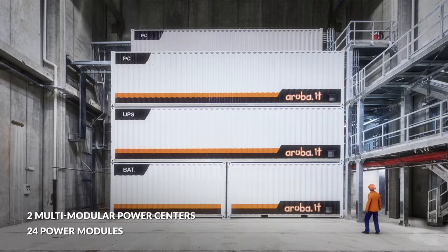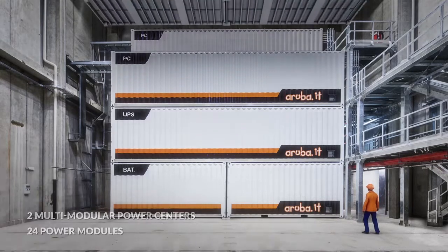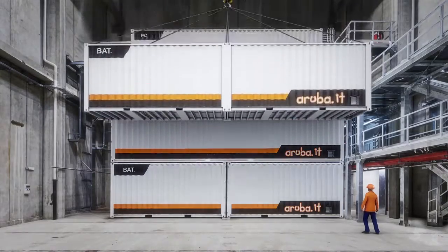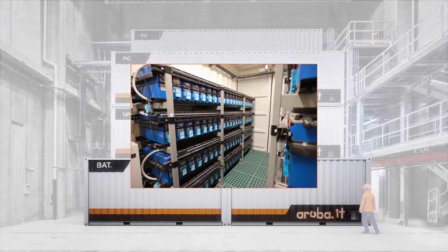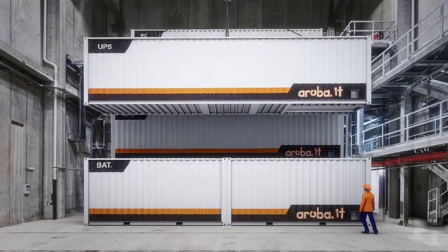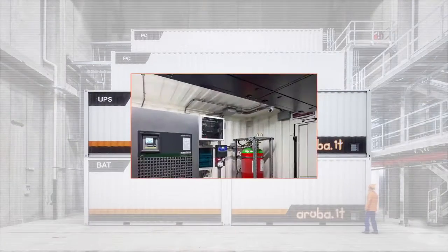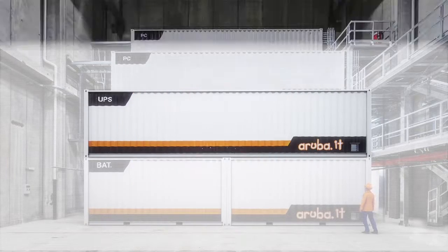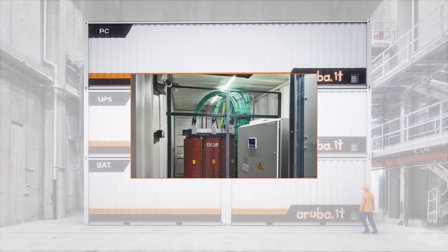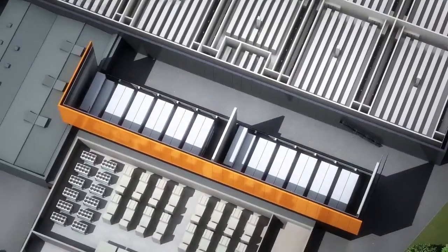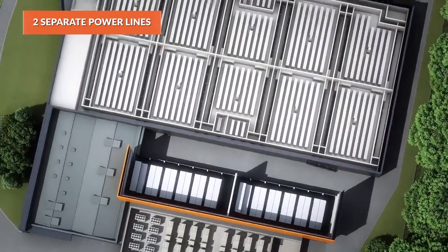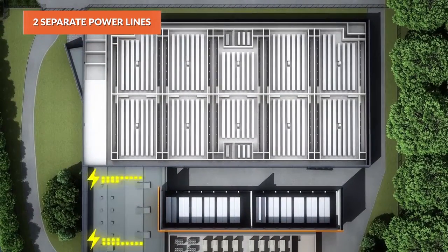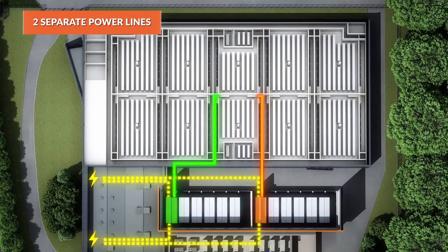The individual module consists of 4 containers with scalable and replaceable components. The 2 lower modules house the batteries. The central module, the UPS systems, and the upper block, the mains board and transformer. Each data room is connected to 2 power lines, each from a module located in a separate power center unit.